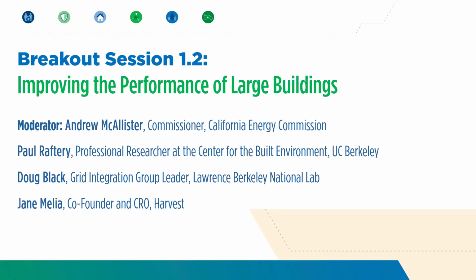So these are not small barriers to overcome, and you have to have the capital for these. To address the urgency of these things in a feasible way, you need a strategic plan for the building, capturing as many synergies with existing activities as possible, so you do this as cost effectively as you can. You don't just jump in and replace your boiler with an air to water heat pump. Maybe you wait until the end of your chiller's life, plan for that project, understand your constraints and your actual loads. Then you replace the chiller and boiler with an air to water heat pump plant, maybe one that does heat recovery as well.